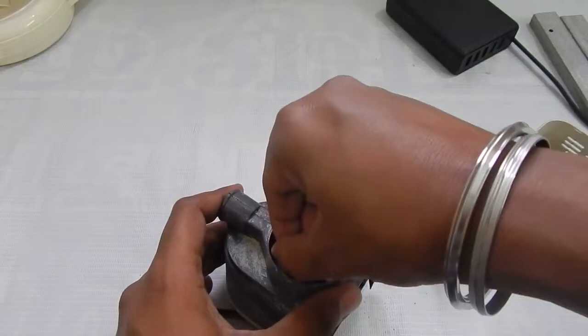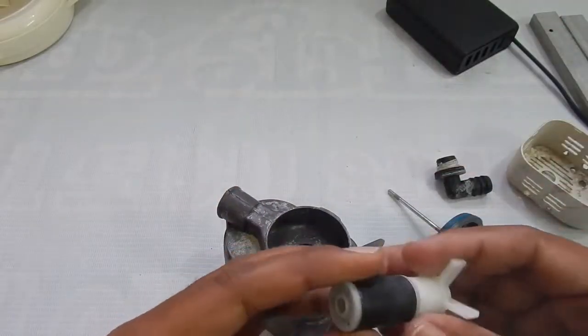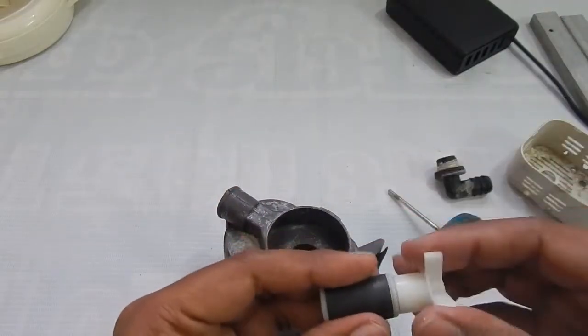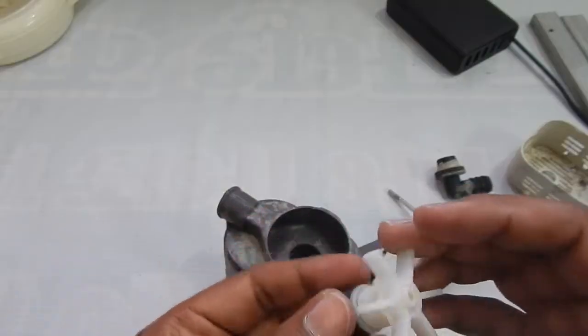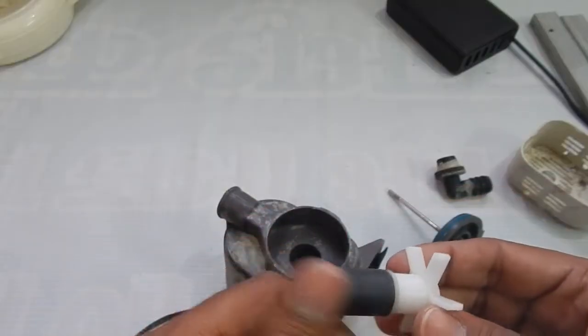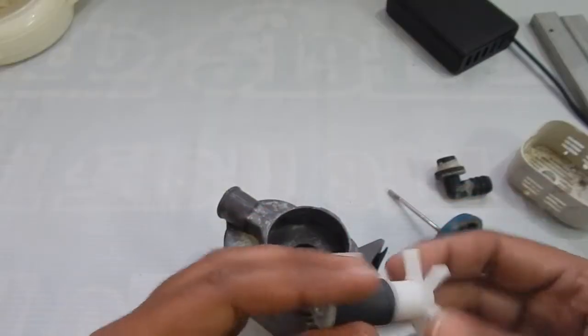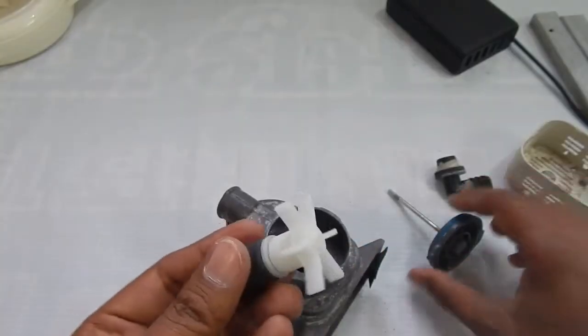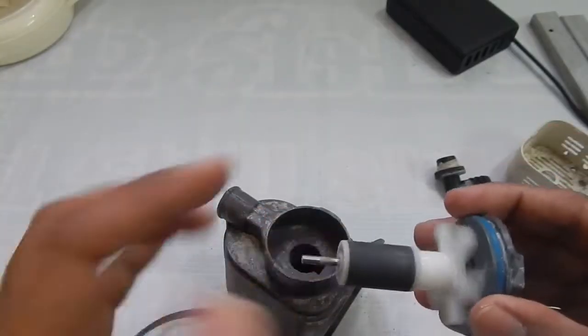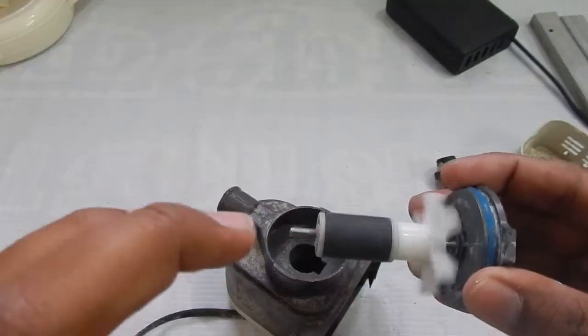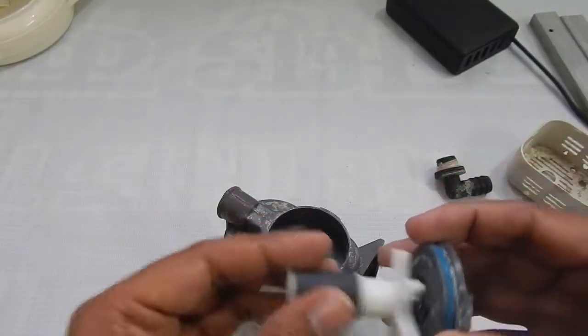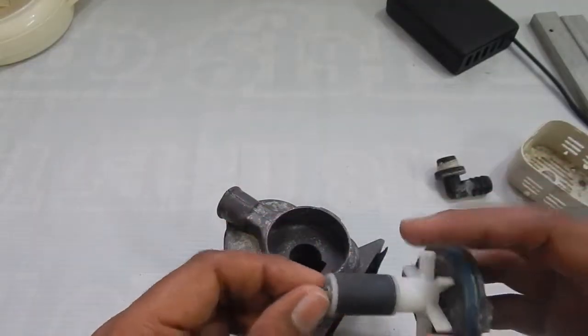So let's take the impeller out. Looking at it, you can see the impeller is also in very pristine condition. There is no damage, no gunk, no algae buildup, or calcium scale buildup. So the pump should have absolutely no problem rotating on the shaft, as you can see it is easily able to rotate. So we can see the problem is not in the impeller.